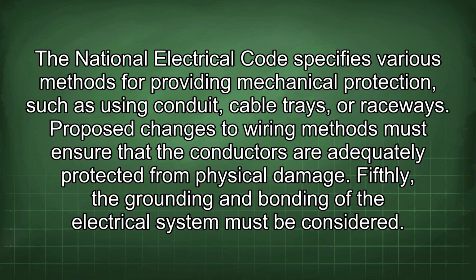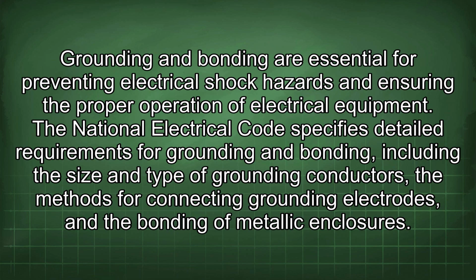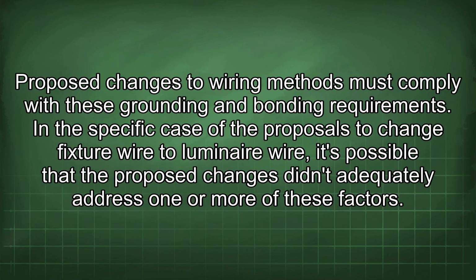Fifthly, the grounding and bonding of the electrical system must be considered. Grounding and bonding are essential for preventing electrical shock hazards and ensuring the proper operation of electrical equipment. The National Electrical Code specifies detailed requirements for grounding and bonding, including the size and type of grounding conductors, the methods for connecting grounding electrodes, and the bonding of metallic enclosures. Proposed changes to wiring methods must comply with these grounding and bonding requirements.